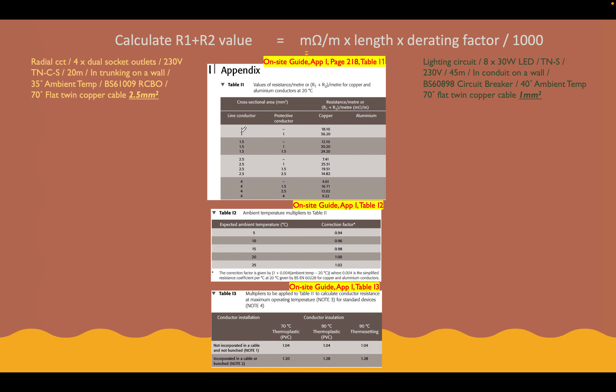For example, we had a 1mm cable on our lighting circuit, and for our protective conductor, let's say we've got a 1mm protective conductor, which it usually would be. We'd then use 36.20 as our milliohms per metre value.